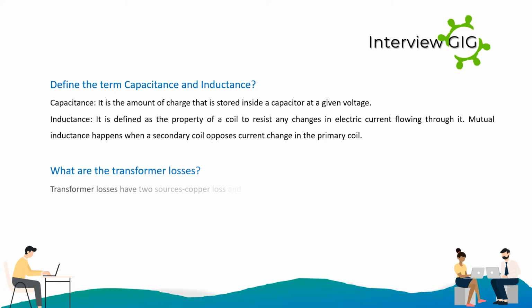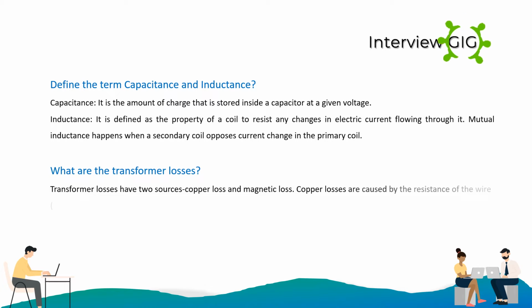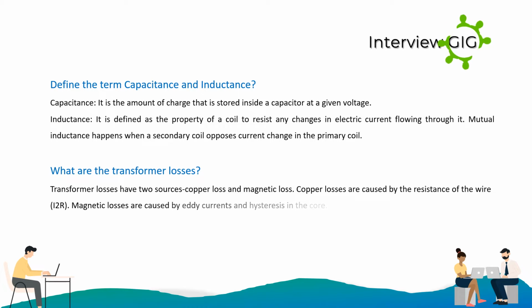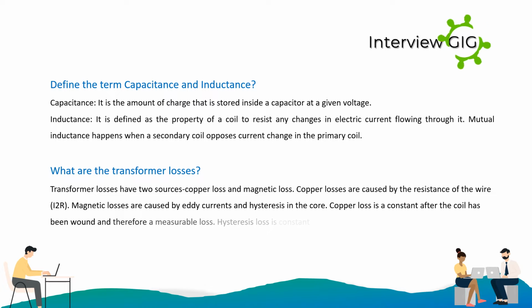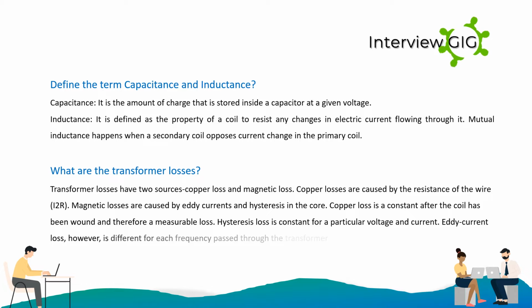What are the transformer losses? Transformer losses have two sources: copper loss and magnetic loss. Copper losses are caused by the resistance of the wire, I²R. Magnetic losses are caused by eddy currents and hysteresis in the core. Copper loss is a constant after the coil has been wound and therefore a measurable loss. Hysteresis loss is constant for a particular voltage and current. Eddy current loss, however, is different for each frequency passed through the transformer.